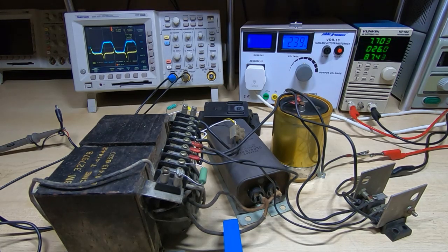As the current in the primary rises, at a certain point we reach resonance in the secondary part of the transformer. We get a sudden increase in the current in the secondary winding, the resonant winding, and that sudden increase in current causes a sudden increase in flux in the secondary part of the transformer, pushing that part of the core into saturation.